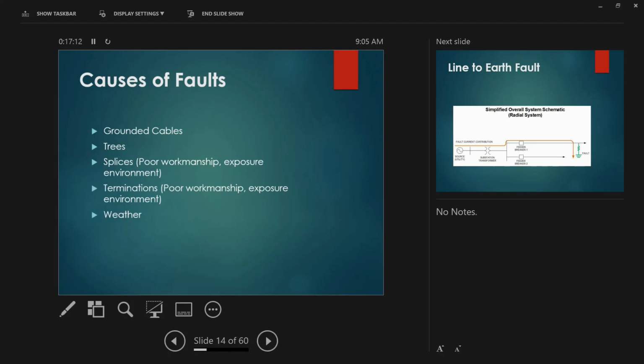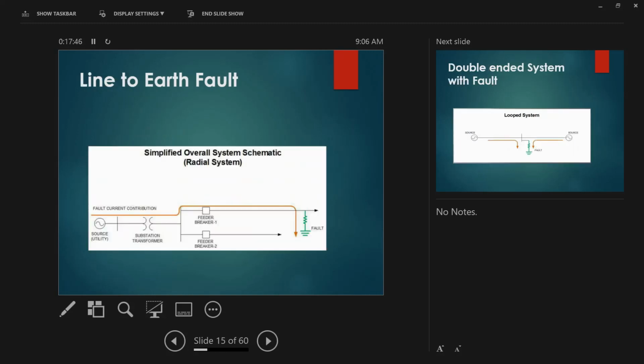Trees, of course, if there is a typhoon in a tropical country, that's a problem that we have there. Poor workmanship for the splicing. Sometimes we do PD and everything, VLF for new installations. Termination problems as well, probably poor workmanship, or because they are exposed to the weather. So those are mostly the common ones on existing installations or after we energize the installation. That's why we came there, to provide them the specific data or test results.